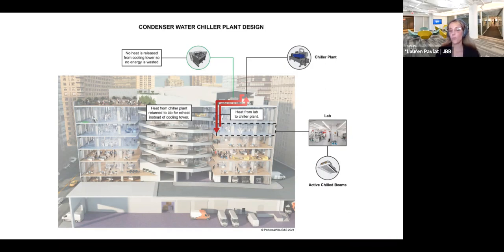It's similar to the previous slide's image, but in the center you have people and equipment creating heat. That heat from the lab goes to the chiller plant. Then instead of going to the cooling tower and outside the building, the condenser water from the chiller plant goes back to the lab and provides heat at typically cooler spaces, like the perimeter. We normally heat with 150 to 180-degree hot water, but instead our units can take in 120-degree condenser water and heat that up.